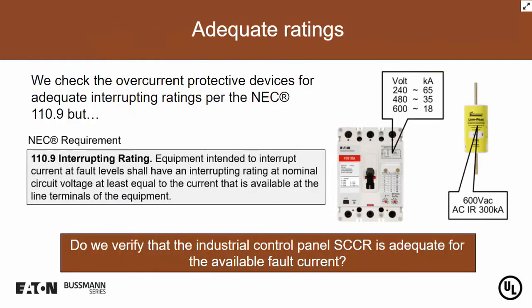All right? So let's look at what adequate ratings we're going to have. Now, we already talked about the SCCR itself. Do we have the adequate interrupting rating of the fuses and of the breakers, the overcurrent protection? So here we talk about 110.9, interrupting ratings, making sure that we have adequate interrupting ratings, just like we have adequate SCCR for the panel. And so 110.9 basically states equipment intended to interrupt current at fault level shall have an interrupting rating at nominal voltage at least equal to the current that is available at the line terminals of the equipment.